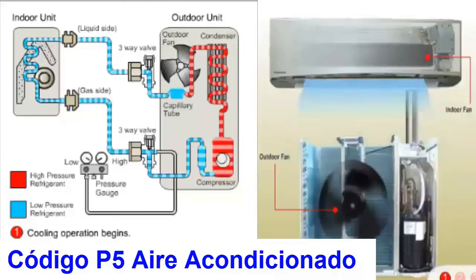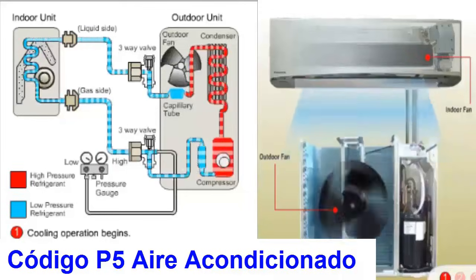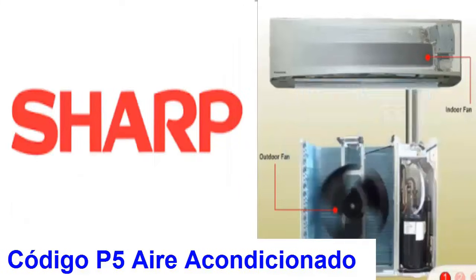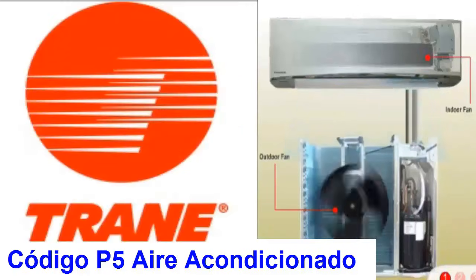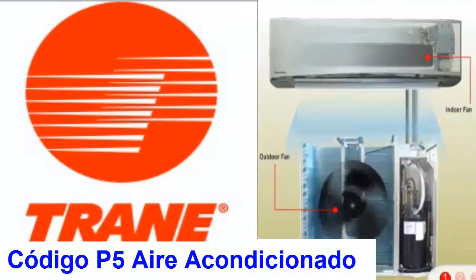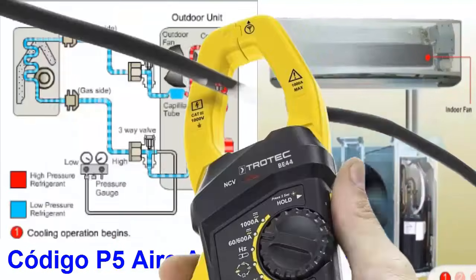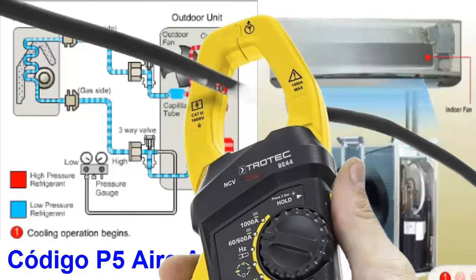2. For Sharp and Trane, the P5 code is related to equipment overcurrent problems, possibly due to an imbalance in the electrical phases. It is recommended to disconnect the electricity from the equipment for several minutes and check if the problem persists. It is suggested to inspect the electrical connections and ensure there are no issues in the power distribution.